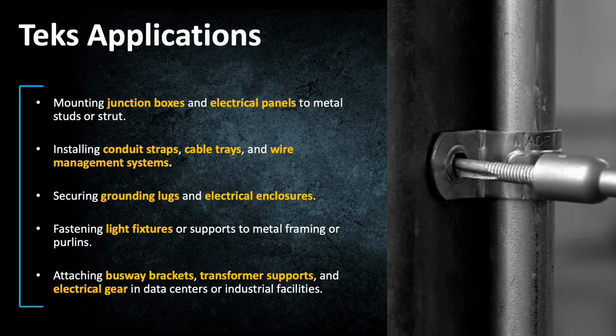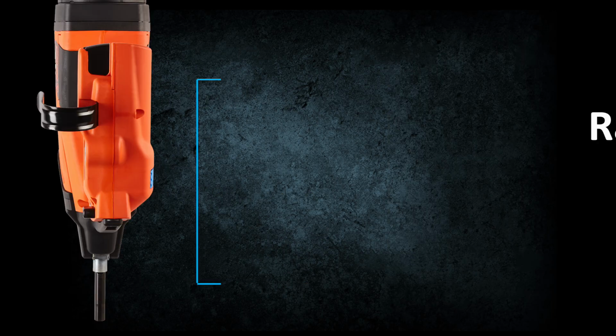Some common electrical applications for Teks include mounting junction boxes and panels to metal studs or strut, installing conduit straps, cable tray and wire management hardware, securing grounding lugs and electrical enclosures, fastening light fixtures or supports to metal framing or purlins, attaching brackets, supports or gear in data centers and industrial facilities. Anywhere you're fastening steel to steel or accessories to metal framing, Teks will likely have an option that fits.